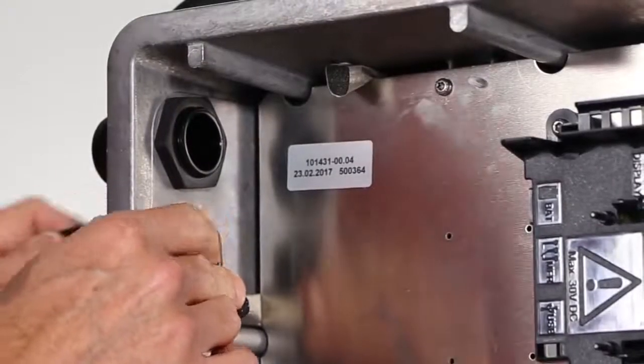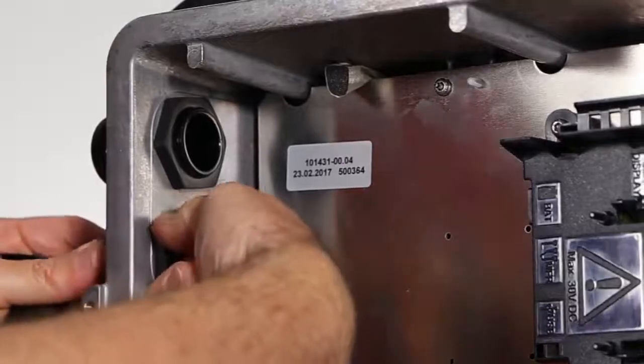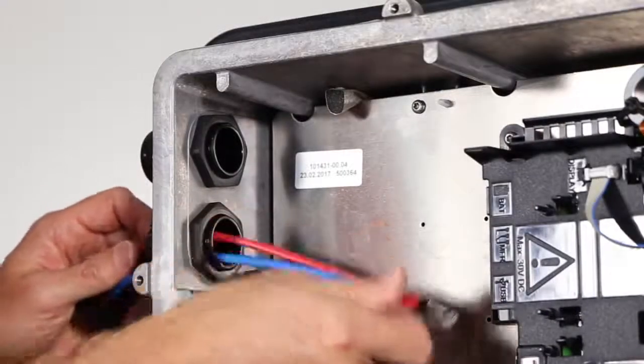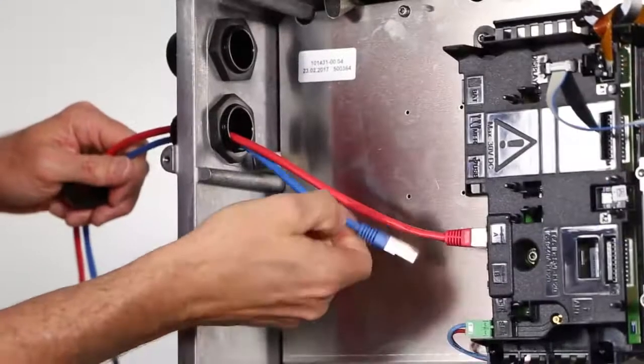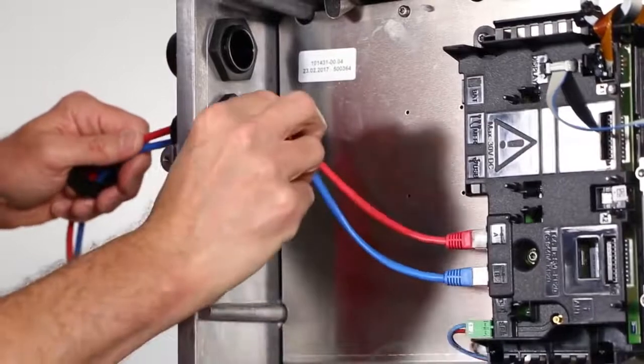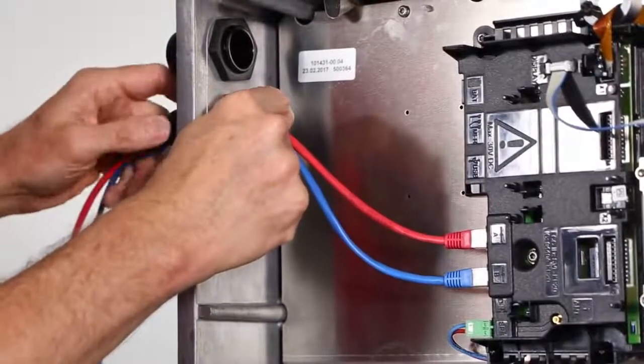For the communications, we bring the ethernet cable through one of the one inch openings and connect it to one of the RJ45 ports on the communications board. Multiple inverter communication boards can be daisy chained together using the second RJ45 port. When daisy chaining, the ethernet cables can be up to 100 meters in length.